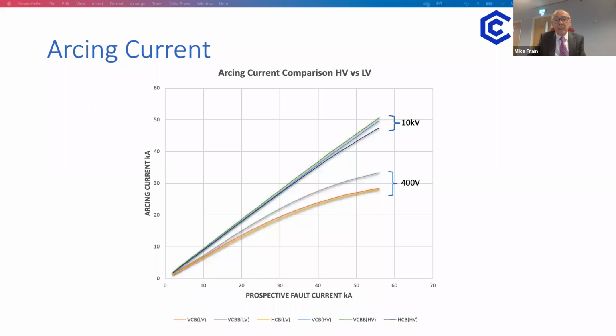To know the level of fault current that can flow into an arc is an essential piece of information for the designer who wishes to know whether his electrical protection systems are going to clear an arc fault quickly, safely, and without damage. Or, as a good friend of mine always says, it could also be sometime next Tuesday. What this graph also says is: will the overcurrent protection clear dangerous arcing faults? After all, most calculations are based upon prospective short circuit current only, and automatic disconnection times for shock protection only as well. So more on this a little bit later on in the presentation.